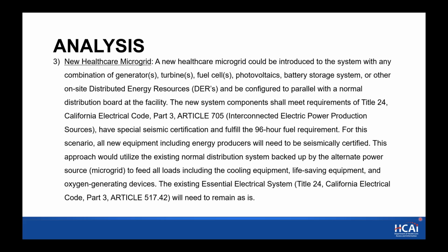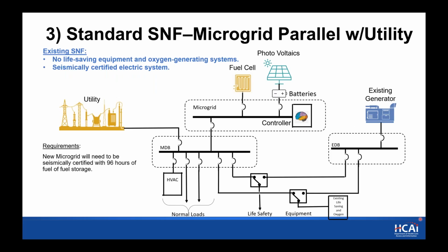This approach would utilize the existing normal distribution system backed up by the alternate power, the microgrid, to feed all loads, including the cooling equipment, life-saving equipment, and oxygen generating devices. The existing essential electrical system, the existing generator and distribution would need to remain as is. Next slide. So here's a couple single lines of that.